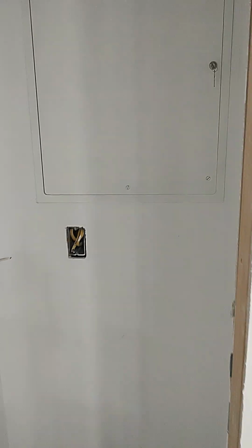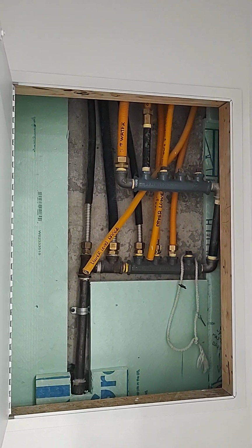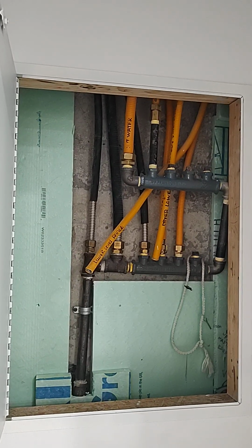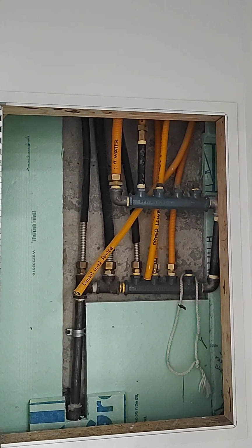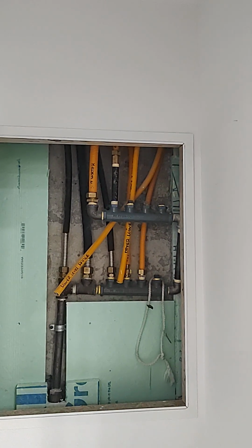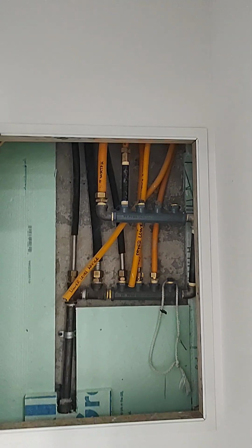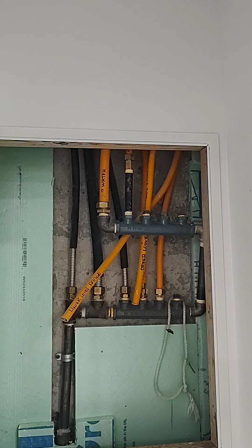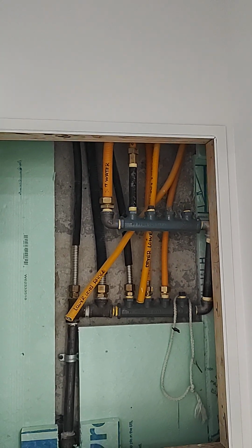Another item. Do you have this at work? So there's 9 gas lines in there, none of them are tagged. The black ones came with the structure. The yellow ProFlex I put in myself, and we have tags ordered that will hang on the manifold indicating what line goes to what gas device. You know, for now we just marked them with marker.